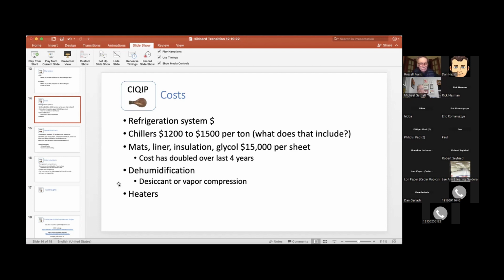Sure. So heaters, I've seen a range of heaters in clubs. The one I was in, we were using basically some industrial heaters you'd see in a warehouse or a workshop. Problem with those is it's very difficult to control where the air is going. It's hard to deflect that air so it doesn't hit the floor, because if any of that moving air hits the floor, it scallops the ice — it dehydrates it. You'll get ripples because the wind is sucking the moisture right out of the ice. So it's best to put in something you can duct. If you can get duct work on it, use horizontal discharges and make sure it doesn't hit your floor, you're fine. The biggest thing is to size it to give you 40, 45 degrees and not cost you a fortune to do it.